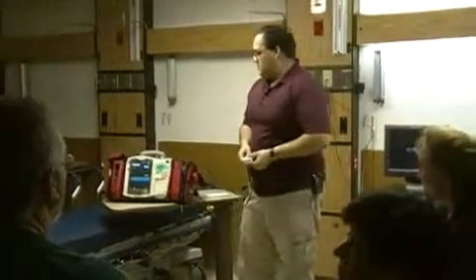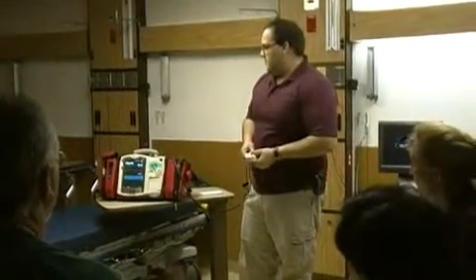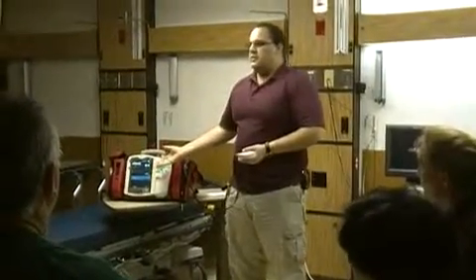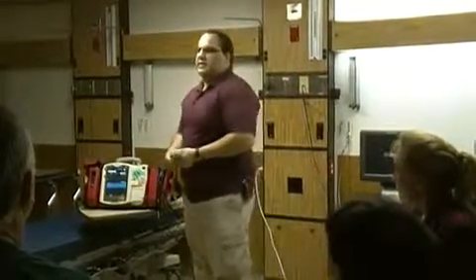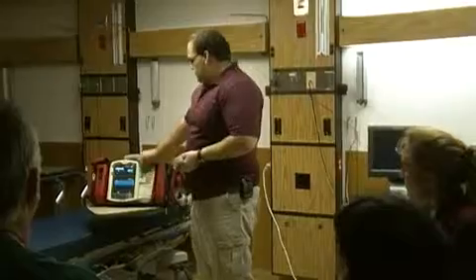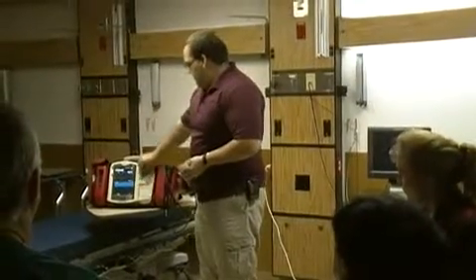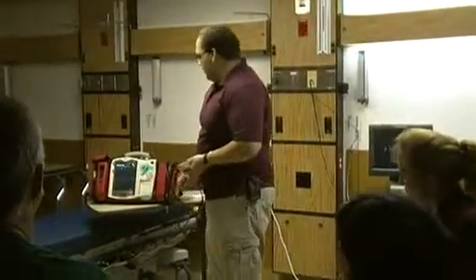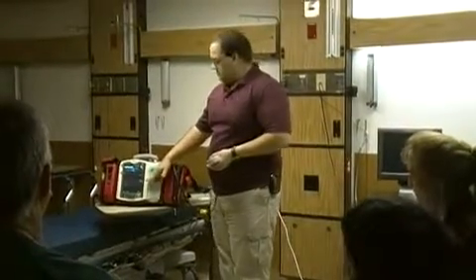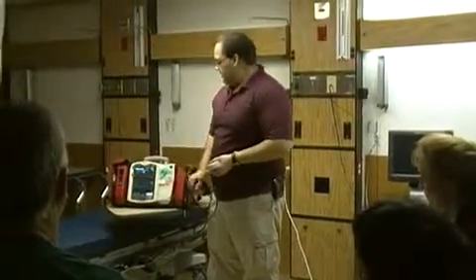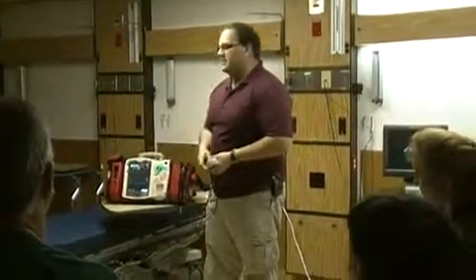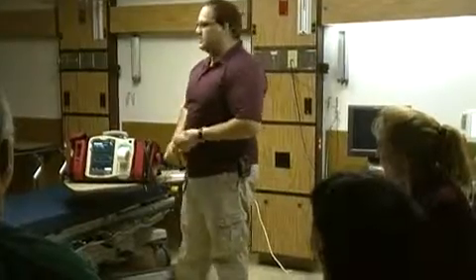And as a matter of fact, all electricity is going to be passed through this transducer. Analyzing heart rhythm. Do not touch the patient. As I said, the AED will talk you through. No shock advised. It'll give you a no shock or shock, pause if needed, tell you when to begin your compressions, CPR, again, when to stop, do your rhythm checks. It is currently based on new AHA guidelines. If you're not going to go into AED mode, monitor only mode is one click to the right. And we give the patient monitoring. Right now it's reading as paddle lead because it's picking up the pads lead, which is this transducer, which is telling it that it's a paddle lead.